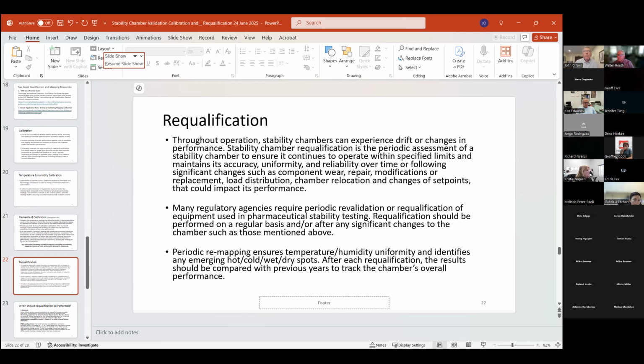Throughout operation, stability chambers can experience drift or changes in performance. Requalification is the periodic assessment of a stability chamber to ensure it continues to operate within the specs and all the required accuracy, uniformity, and reliability over time. So whenever there's a significant change, it could be non-like for like parts, component wear, repairs, modifications, or replacements. And as we mentioned before, load distribution.